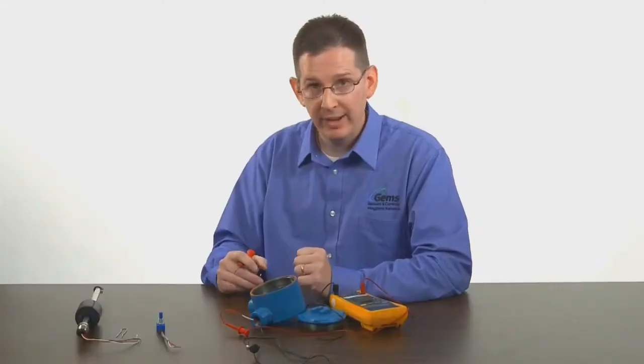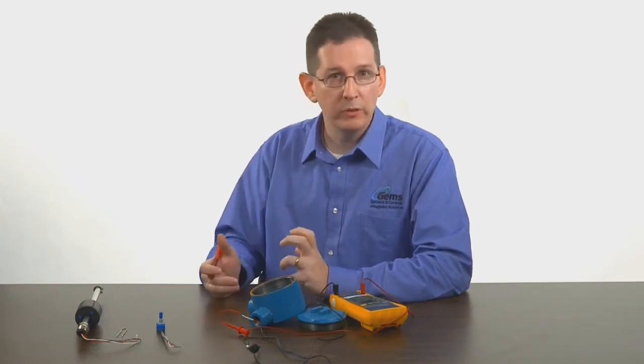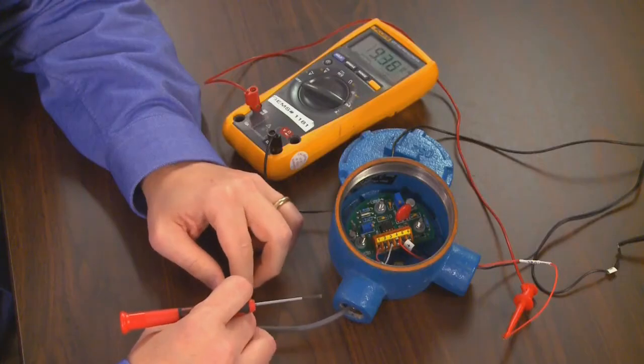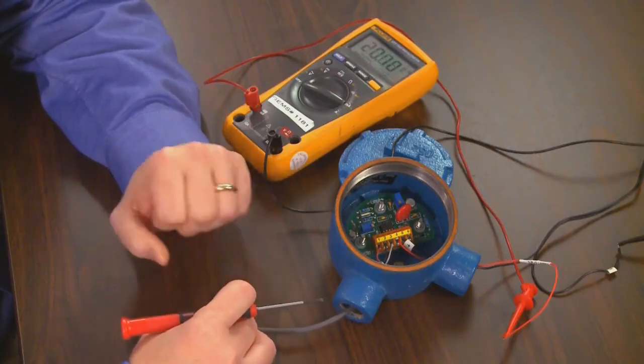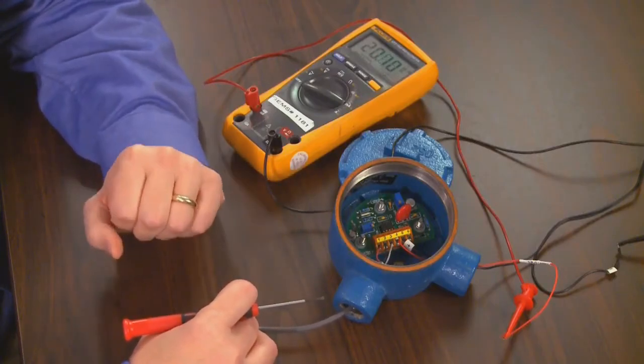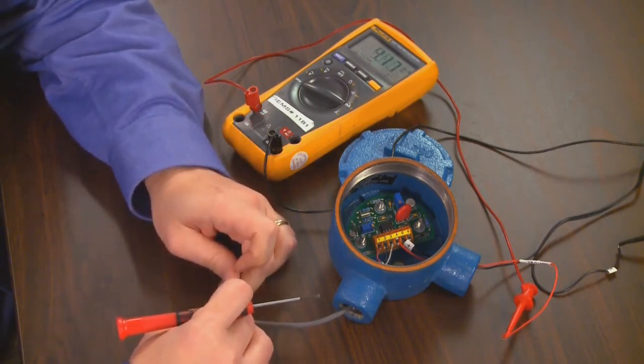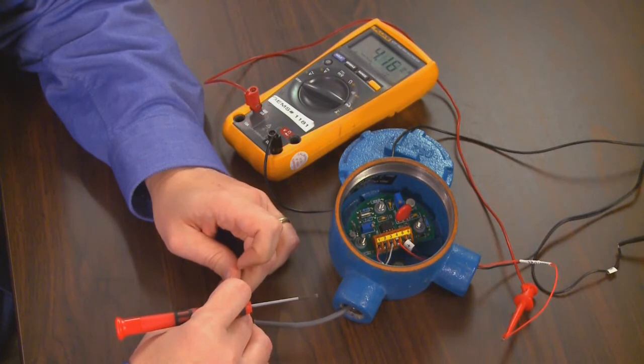Once you have your potentiometer connected we want to establish the direction of raising and lowering its output. Turning the potentiometer clockwise, you'll notice on the multimeter that the output goes towards 20 milliamps. Counterclockwise, the output drops towards 4 milliamps.